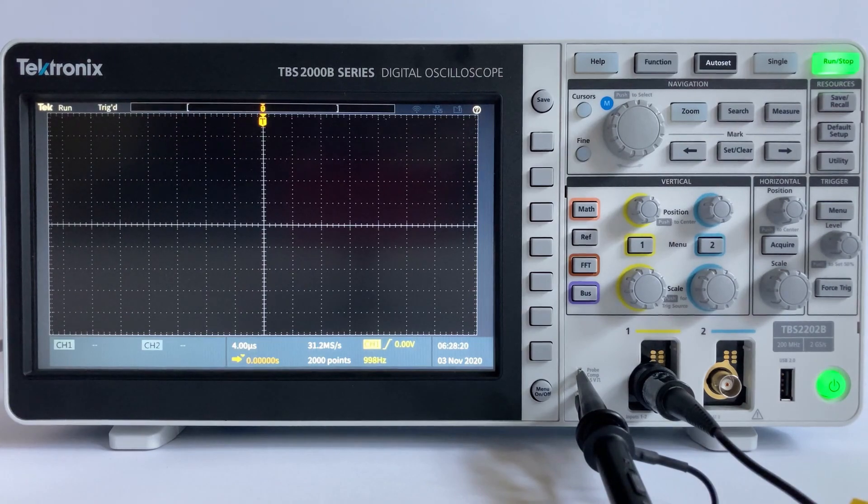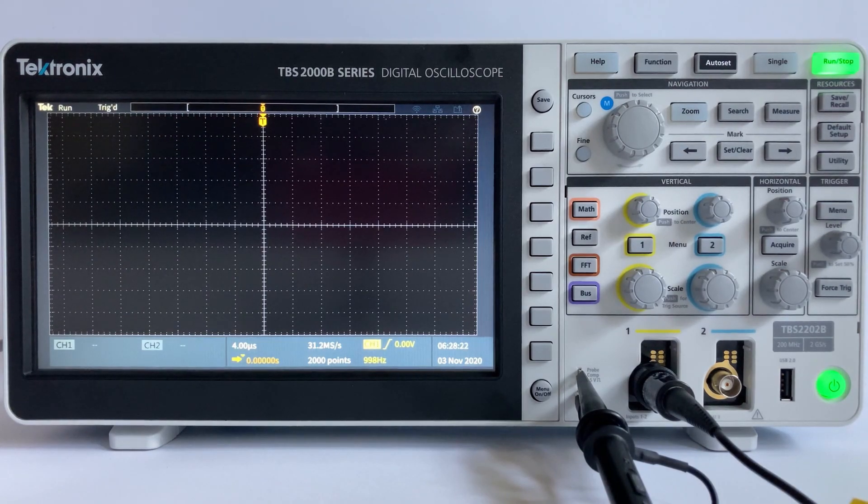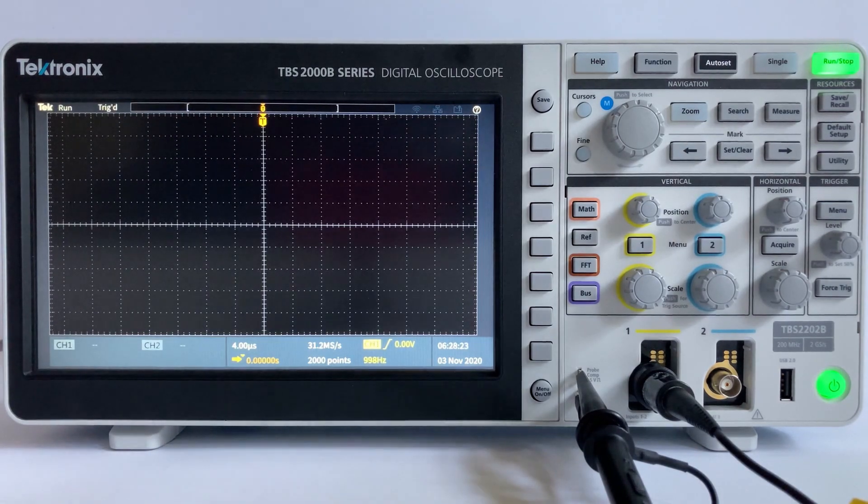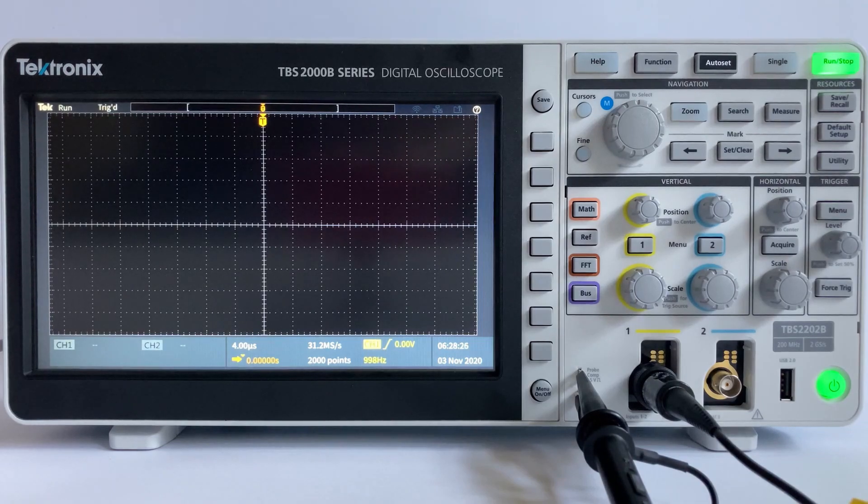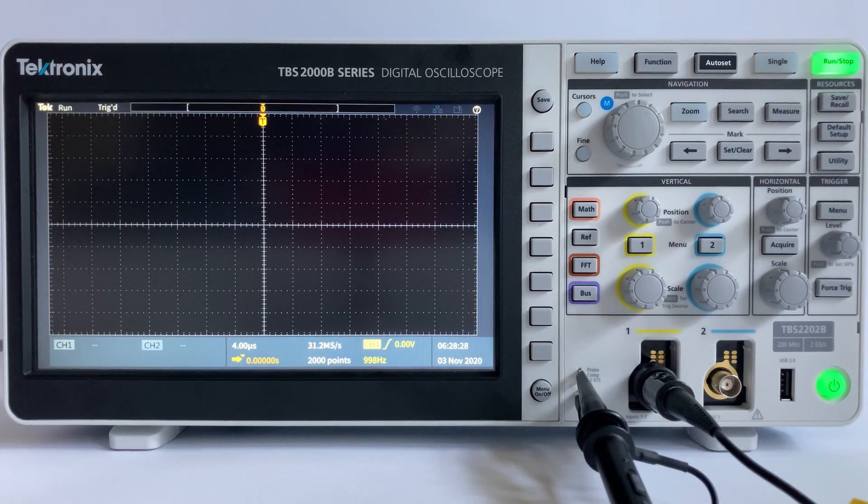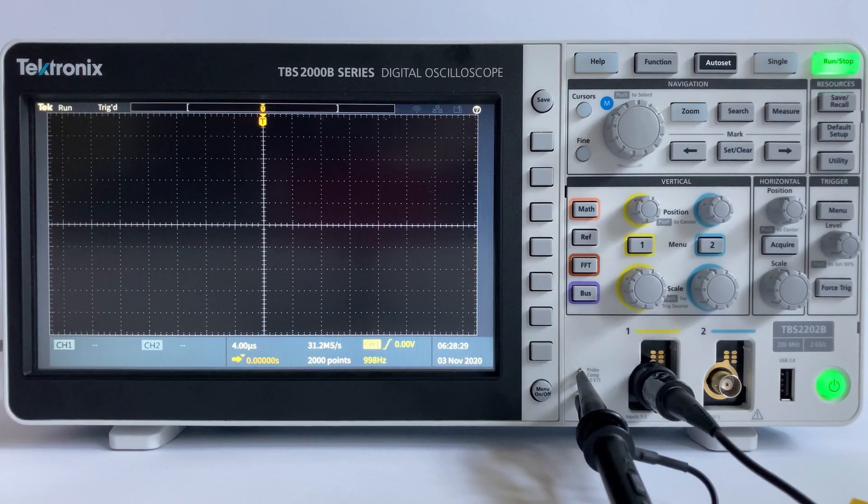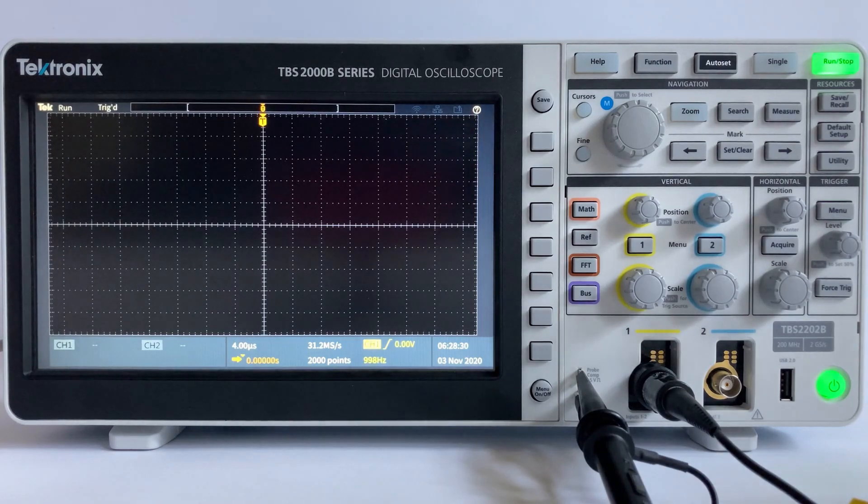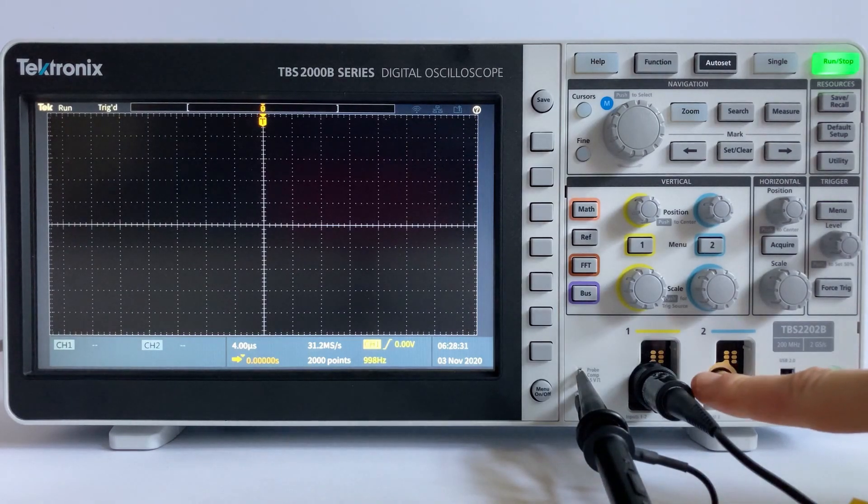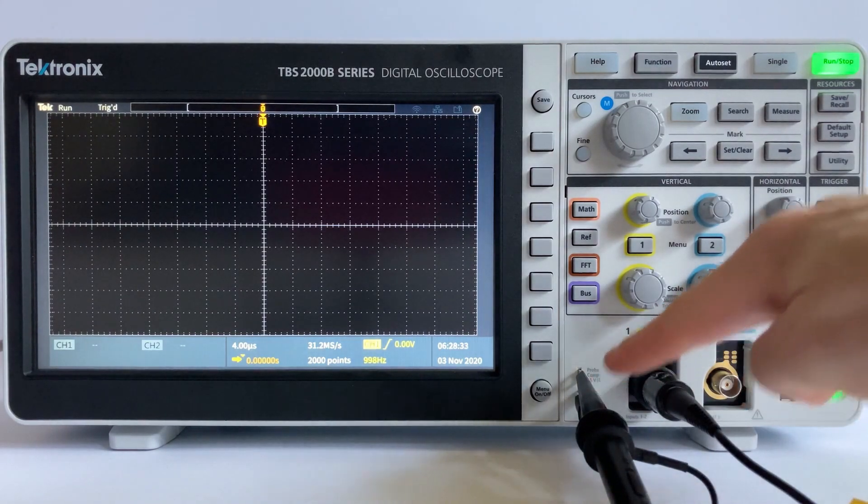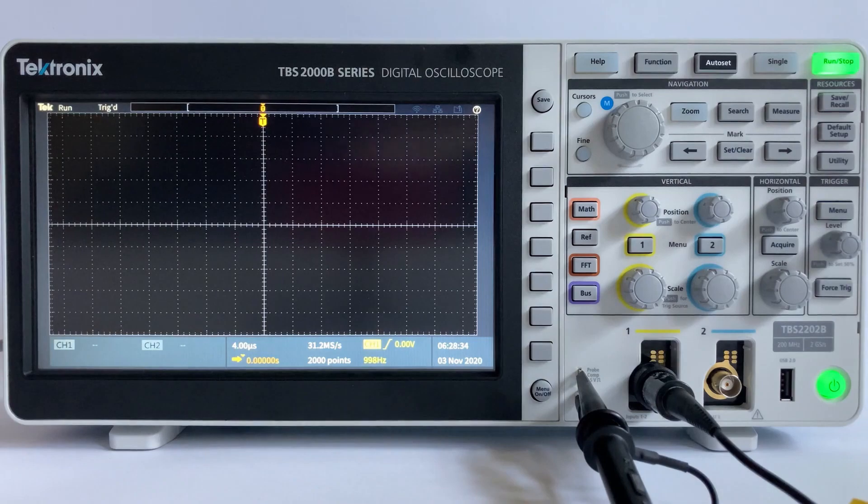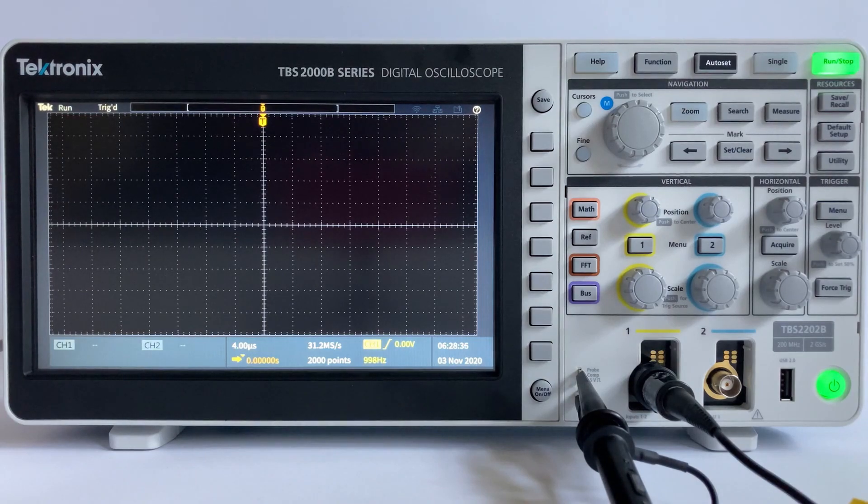Let's do a quick demonstration on how to use the Autoset feature on your oscilloscope. For this demonstration, I will be using a TBS2000B, and I have a 10x attenuation passive probe connected to the probe compensation pin. The probe compensation pin should output a 5V, 1kHz square waveform.